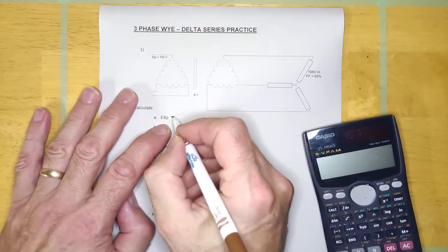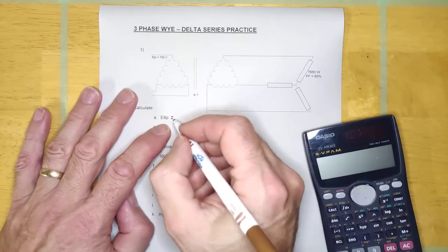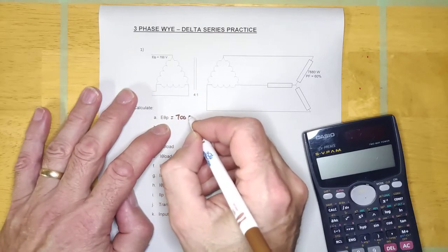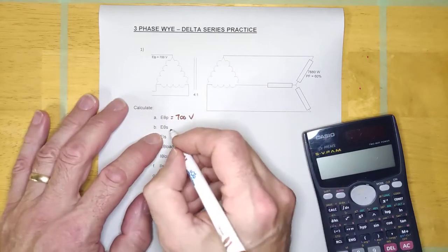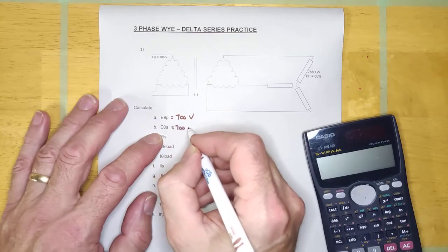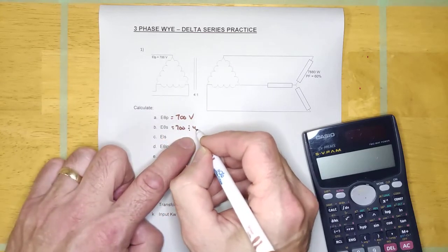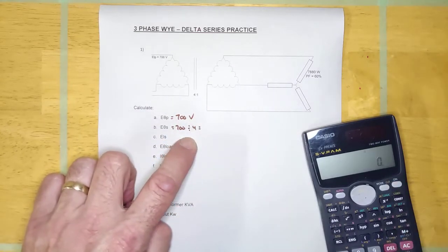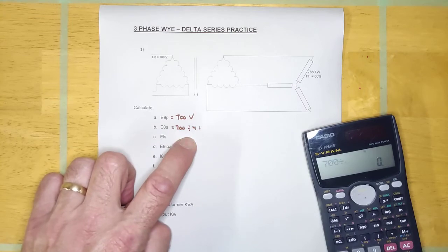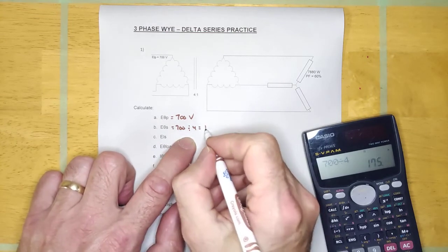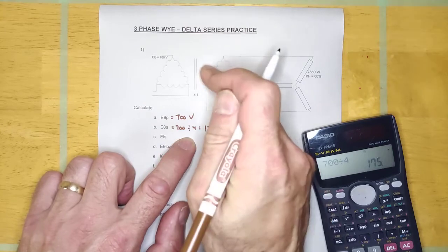E-phase primary looks like it's delta, so that's 700 volts across the transformer. That's going to be 700 divided by 4, because that's our ratio. So let's do that: 700 divided by 4 gives us 175 volts here, okay?